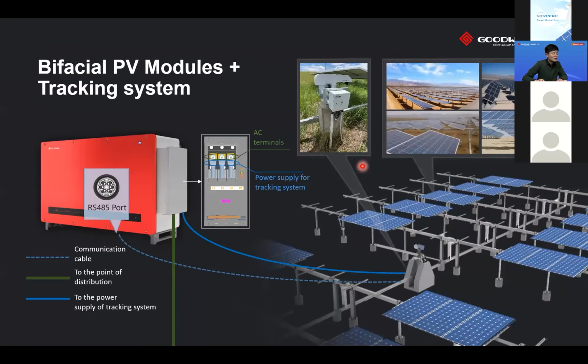About the tracking system, GoodWe has integrated an AC terminal power supply. With this kind of design, the tracking system can get its power supply from our inverter. So users can save the cost of another power supply for the tracking system. GoodWe products already integrate that. It's very easy to maintain and saves cost. Another thing is that with our RS485 port, the tracking system can communicate with our inverters and upload and download information and data to our monitoring system. And you can monitor the tracking system's operation and report everything.